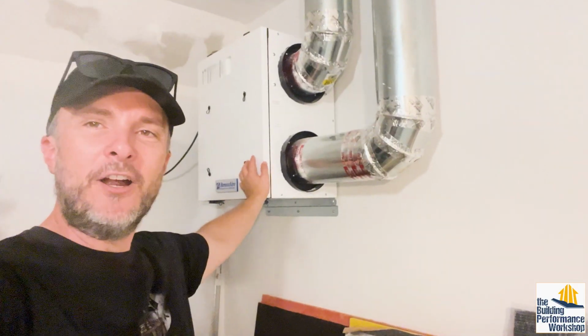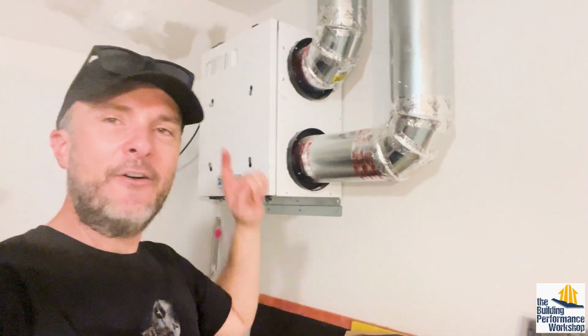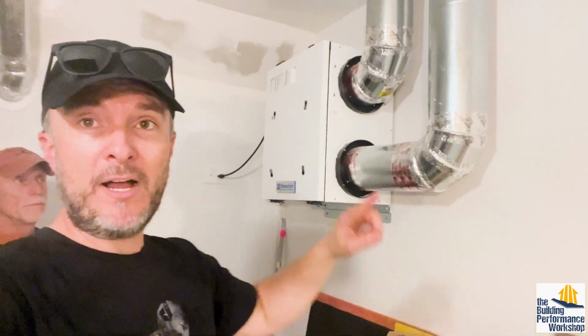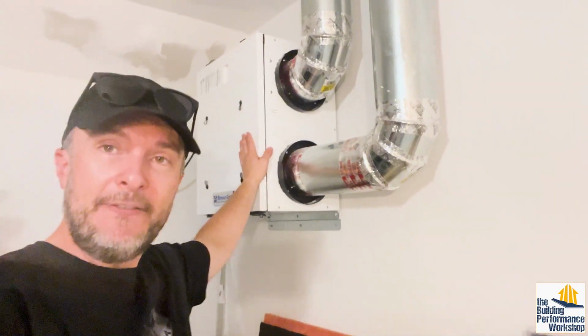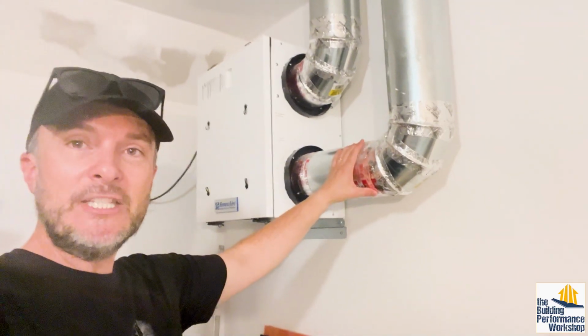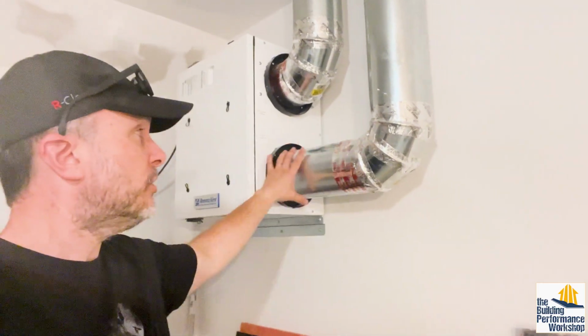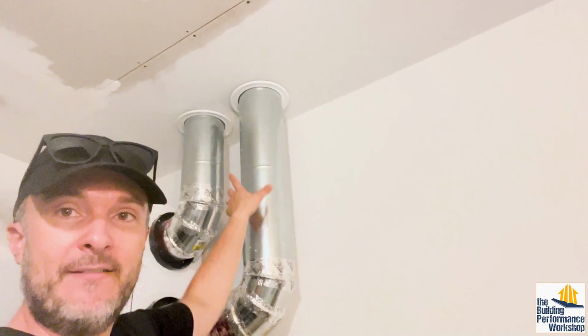One other note about the ERV - it's possible these things are a little loud. In fact, I bet it's going to be way louder than that Bosch heat pump. If it is loud, you just make sure you've got at least 3 feet of run on the fresh air side, which Mark does have here, so he could add a silencer later. It's called a duct silencer.